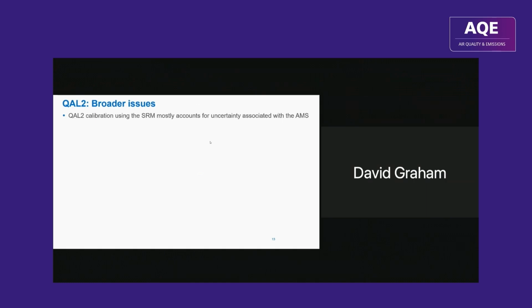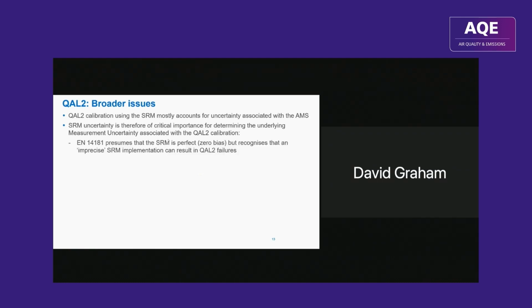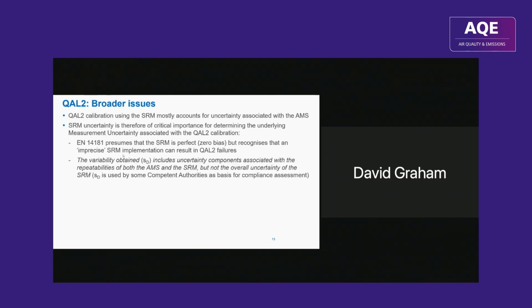In terms of broader issues, it would be fair to say that the QAL2 calibration using the reference method does mostly deal with the uncertainty associated with the AMS, because it calibrates it out. But SRM uncertainty is therefore of critical importance for determining the transferred uncertainty within the QAL2 calibration. 14181 presumes that the SRM is perfect. It doesn't say that, but it's a presumption for zero bias, which clearly can't be true. But it recognizes that an imprecise implementation can result in QAL2 failures. So this is saying if the data scatter contribution from the SRM is too high, you'll fail the variability test.